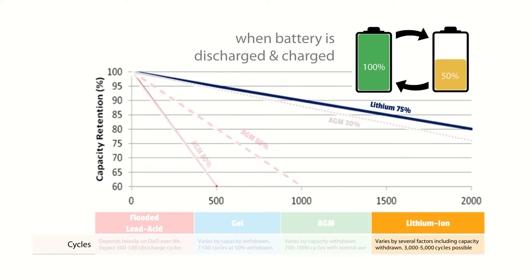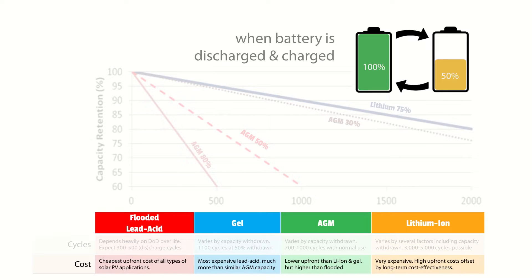The lifespan of a battery is typically rated by the number of cycles in which the battery is charged and discharged. When properly maintained, lead acid batteries will typically last between 7 to 10 years or around 1,000 cycles. Lithium ion batteries on the other hand may last around 20 years or between 3,000 to 5,000 cycles. The longer lifespan of lithium ion batteries could largely offset their cost difference, which is typically two and a half to three times more than traditional lead acid batteries, making lithium ion a good option when considering total lifespan.